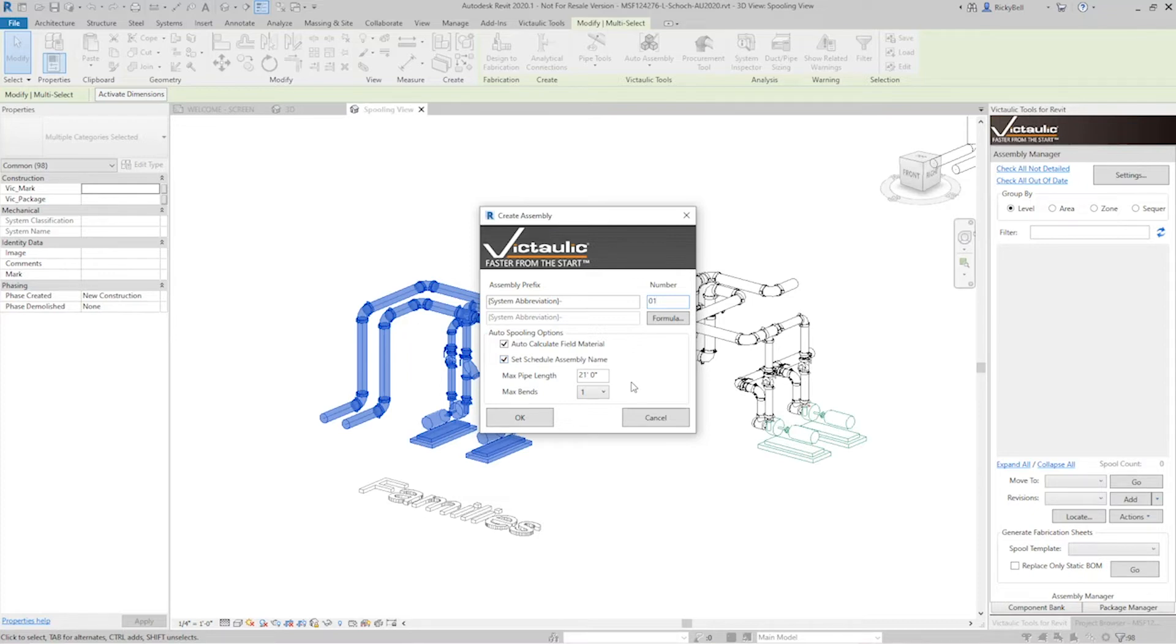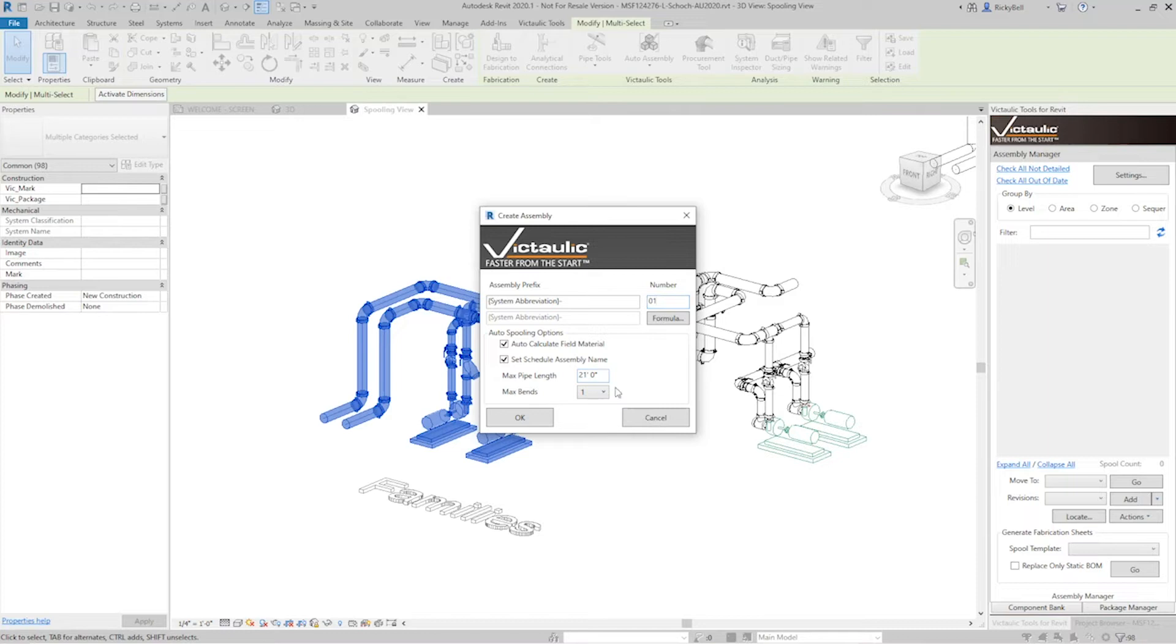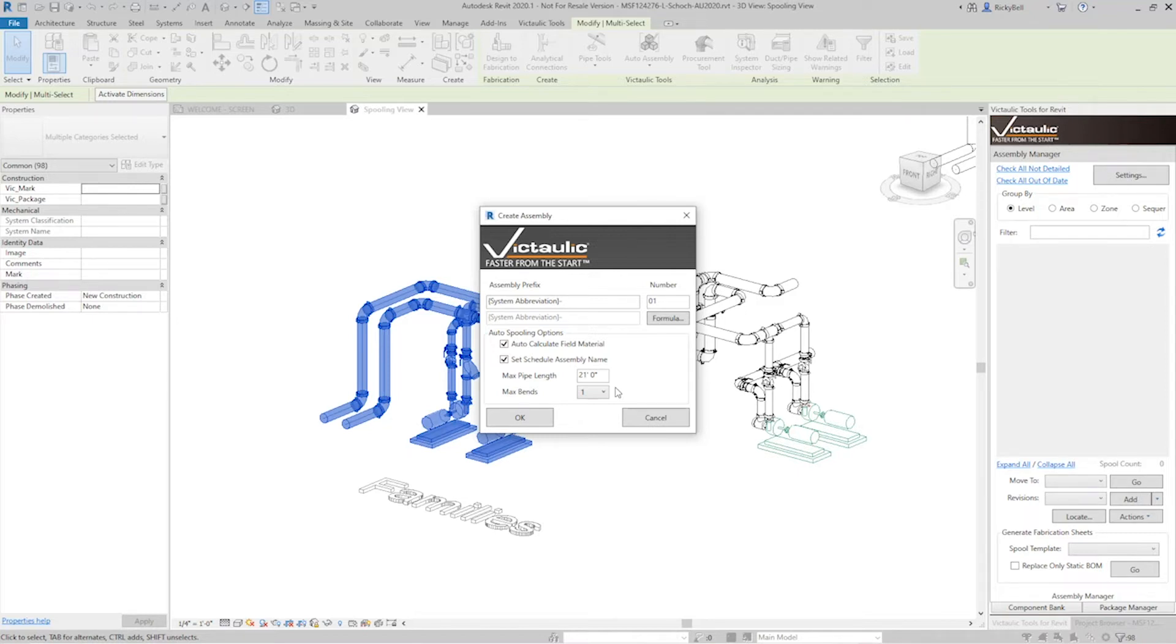And here at the bottom, these are the ones that really make a difference here. The maximum pipe length for a spool, this will include the length of any fittings on the end. I'm going to have set at 21 feet. That means if there's any pieces of pipe with the combination of fittings that falls above 21 feet, those will not get assigned to an assembly and they will remain white. So there's a visual indicator that it broke the rules of the auto assembly. Now the maximum bends at the bottom, this is the number of elbows that you want in your spool. So typically you'd probably want this to be at one so you have very linear spool drawings. But if you wanted larger selections, you could set this up to two or three and see how it changes the way auto assembly works.